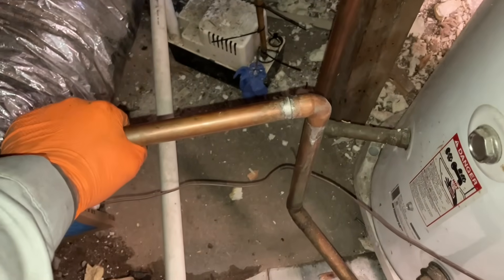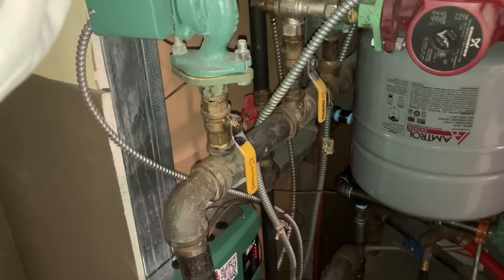Let's see how it is by the indirect. That's cold — making its way back to the boiler. That's domestic cold, domestic hot. Space heating from boiler out and back to boiler. I would like this to be hotter. My zone is calling. At least that one's getting hot now. This one's not doing a thing. Let's purge.